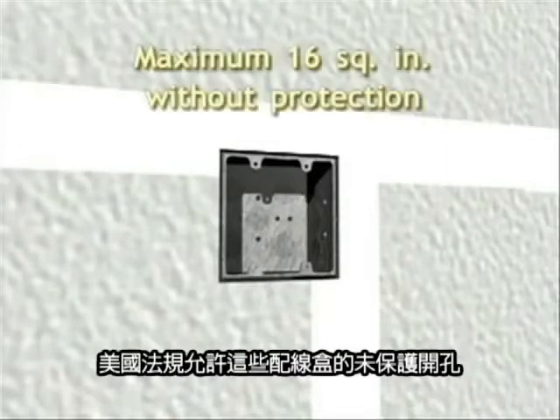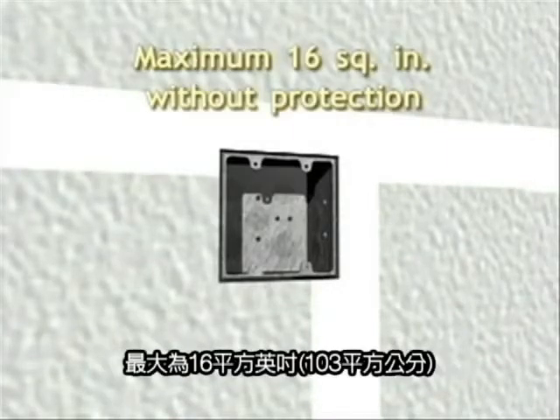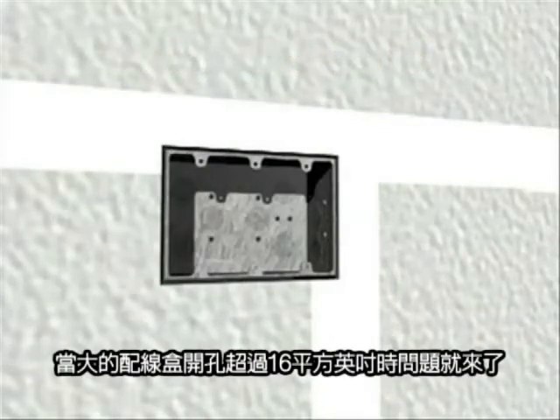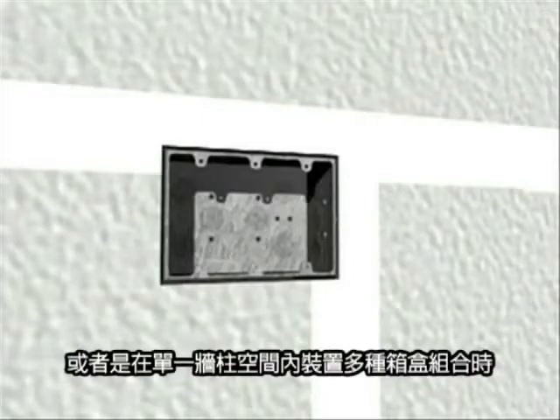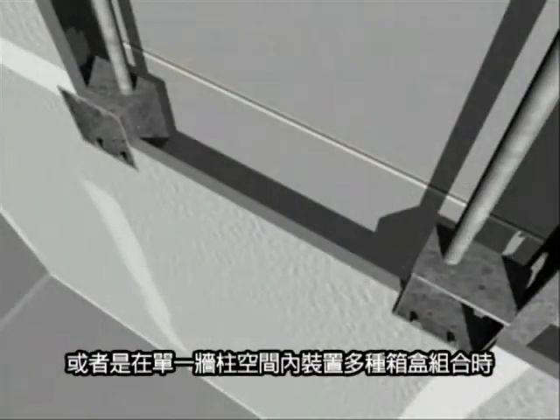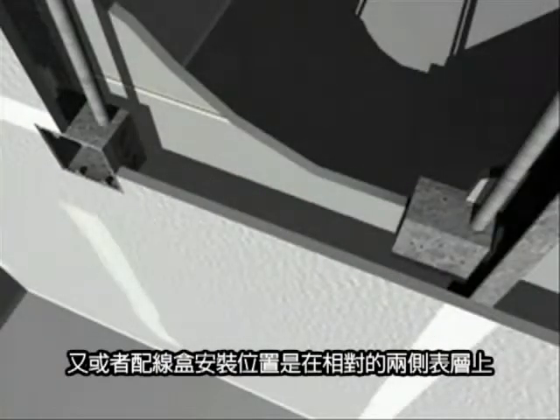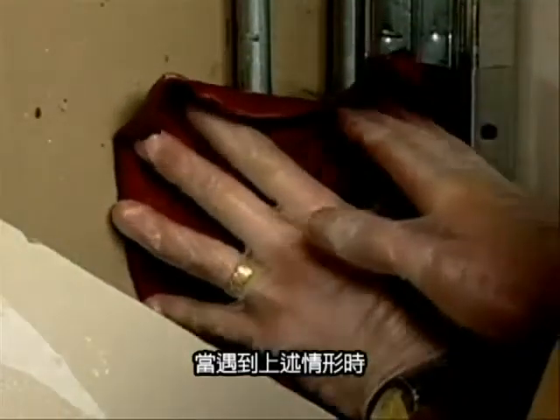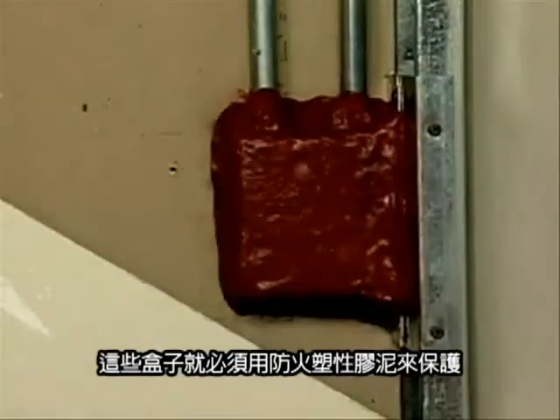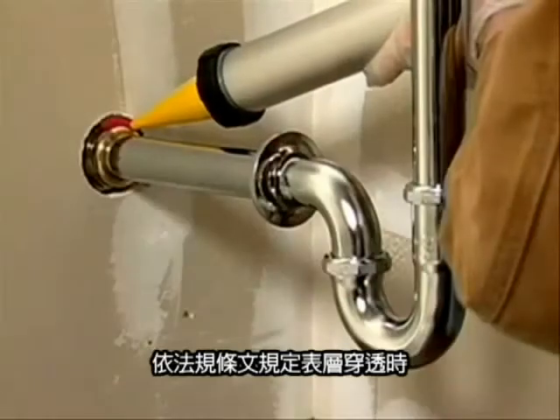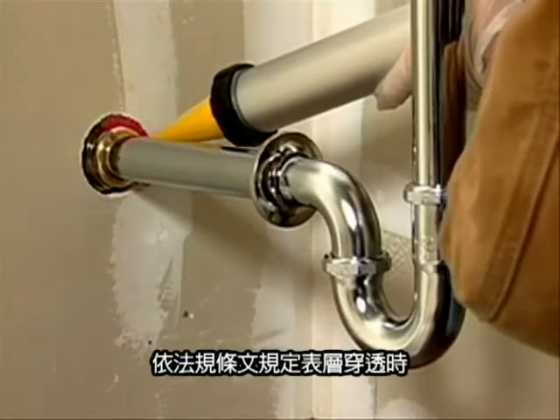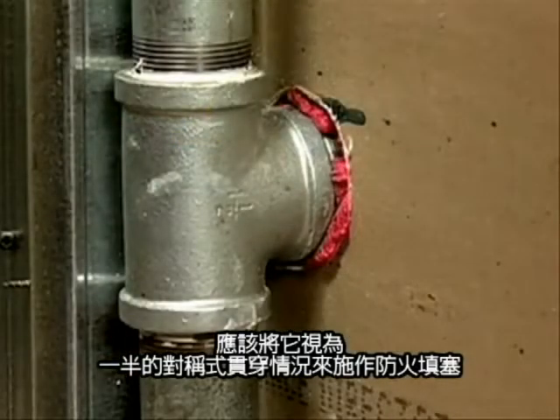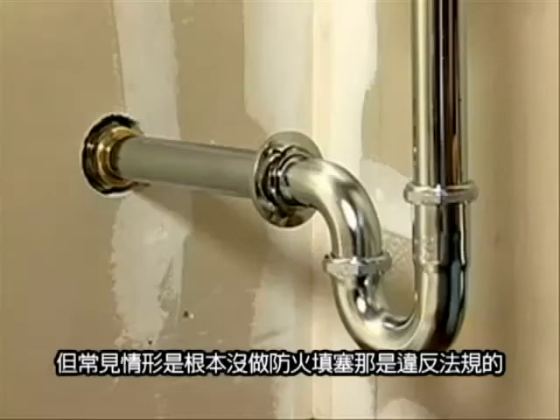Codes permit an opening for these boxes of up to a maximum of 16 square inches without protection. This presents a problem when the 16 square inch limit is exceeded with a larger box, a combination of multiple boxes within a single stud cavity, or boxes on opposing membranes. When these conditions are encountered, the boxes must be protected with fire stop putty pads. Code language mandates that membrane penetrations shall be sealed as half of a symmetrical through penetration, but more often they are not sealed at all, which is a code violation.